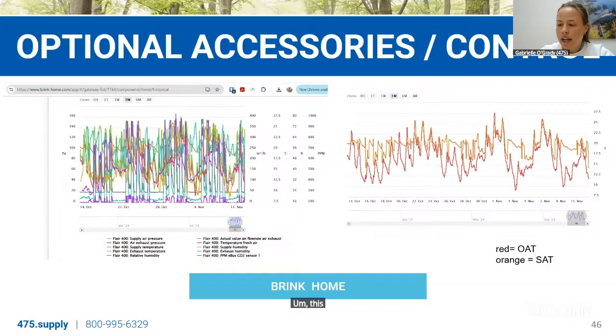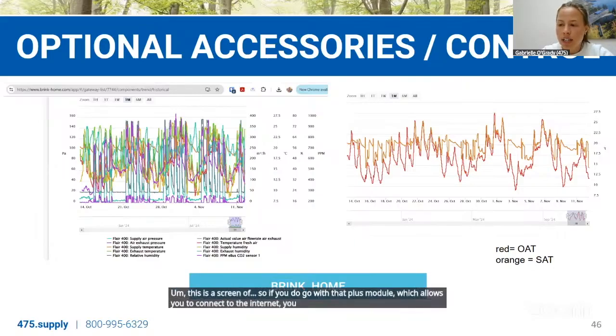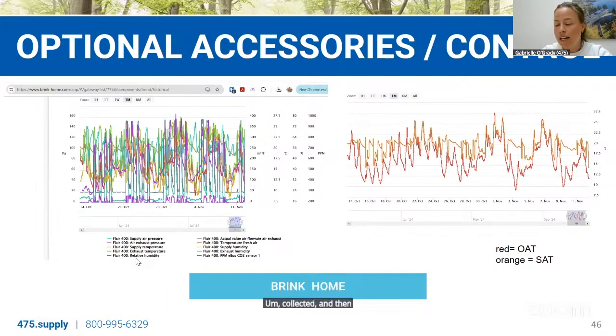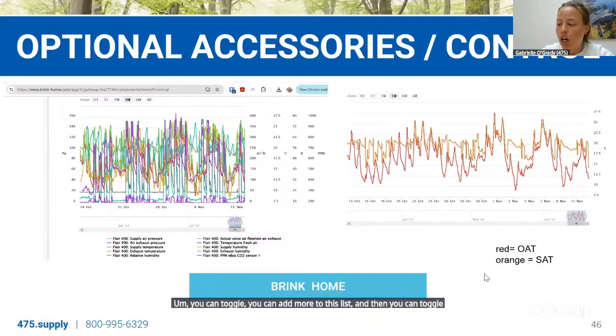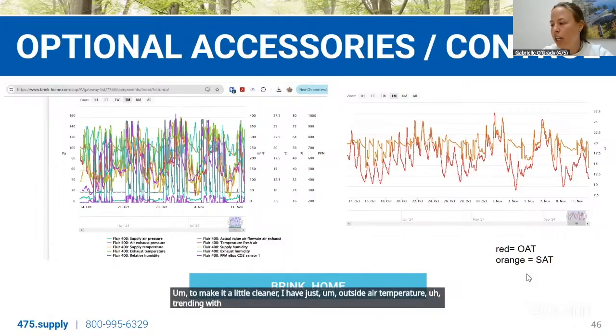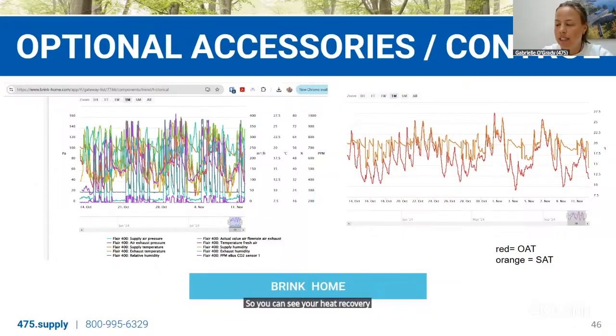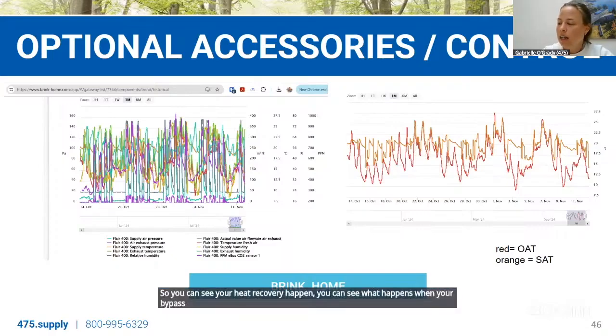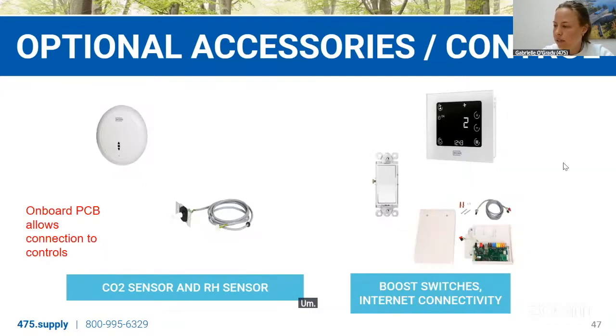This is a screen of, if you do go with that plus module, which allows you to connect to the internet, you then can log into the Brink home page. It's a browser, and this is just showing some of the parameters that are collected and can also be trended. So it's a great way to see what's going on with the unit itself. You can add more to this list, and then you can toggle them on and off to make it a little cleaner. I have just outside air temperature trending with supply air temperature there on the right. So you can see your heat recovery happen. You can see what happens when your bypass opens. Very neat there. And as mentioned, our optional controls.